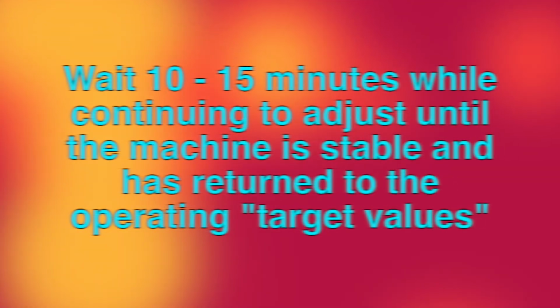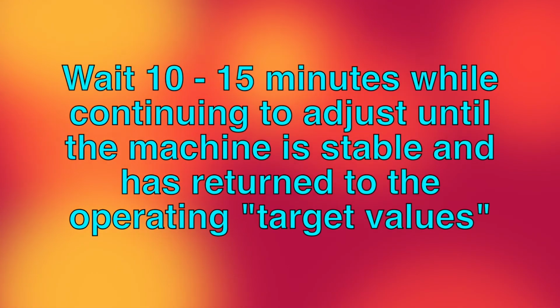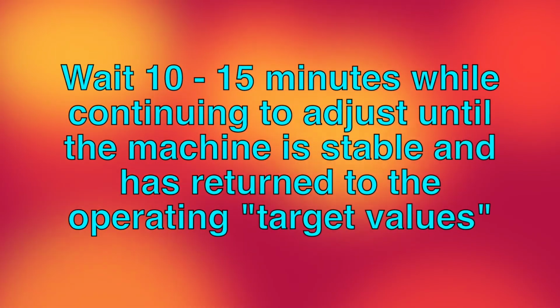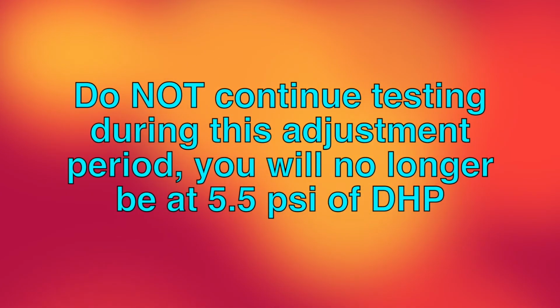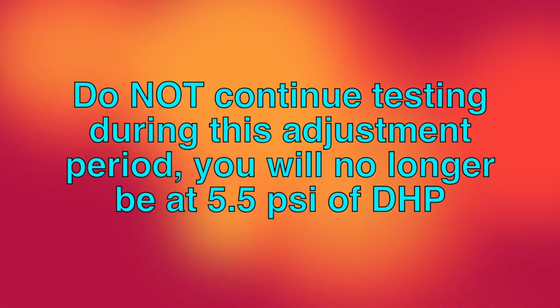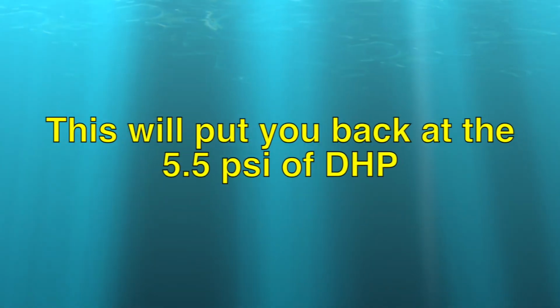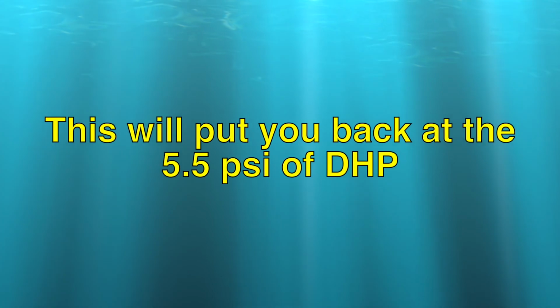Whichever process you use will require 10 to 15 minutes to restabilize the thermal shock machine. The testing cannot continue during this period. You must wait until your individual target values have been achieved again. This will put you back at the 5.5 psi of dynamic head pressure.